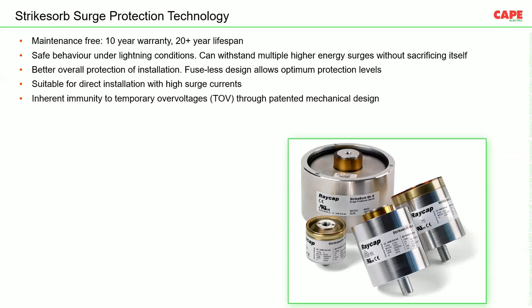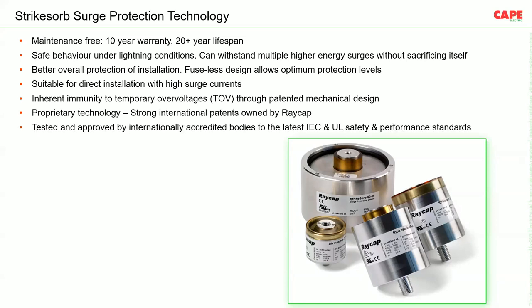These SPDs are again TOV tested. TOV, temporary overvoltage, is one of the most important parameters in an SPD. Normally, an SPD is going to operate when there is a voltage more than the voltage protection level. But sometimes there can be a small overvoltage across an SPD, of 440 volt or maybe more, and that can create a failure in the SPD. So these SPDs have immunity against TOV voltages. Again, these SPDs are tested as per IEC as well as UL. UL is one of the safest standards in the world. We have tested with UL 1449 fourth edition as well as IEC 61643 part 11, 2011.